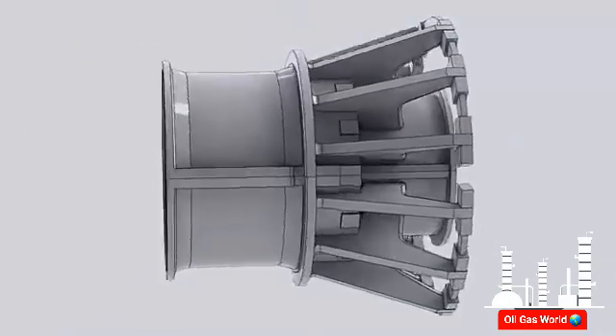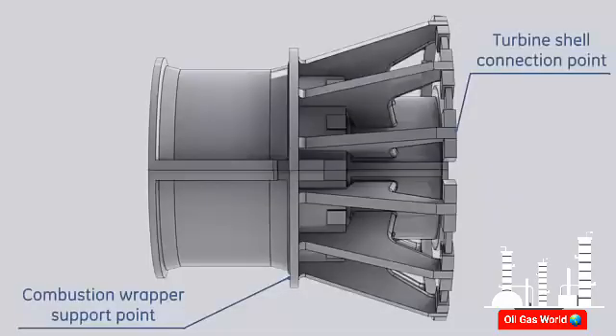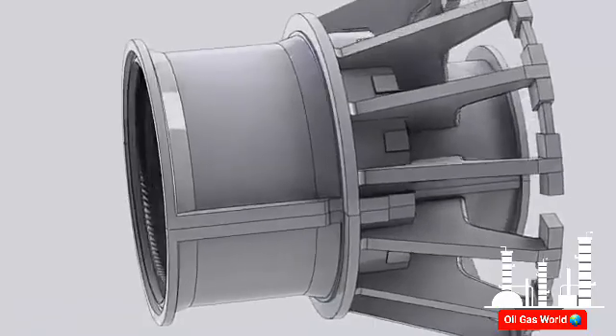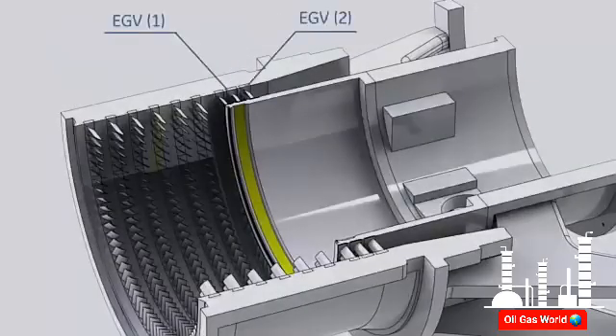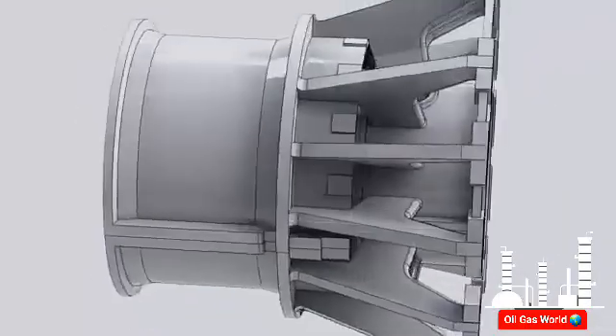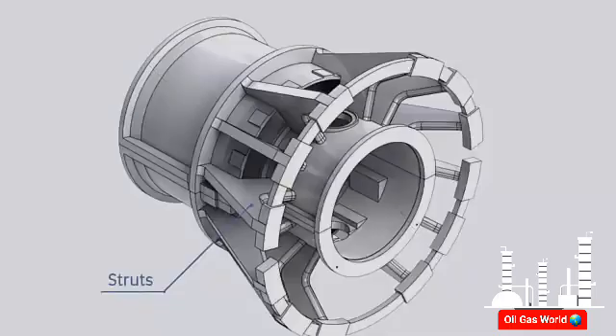The discharge casing is the final portion of the compressor casings and the largest single casting. It is the keystone of the gas turbine structure, connecting the compressor to the turbine section and supporting the combustion system. The discharge casing contains the last seven stages of compressor vanes and two rows of exit guide vanes. It consists of outer and inner cylinders connected by 12 struts, which flare out to meet the large diameter of the turbine shell while providing spacing for transition pieces in between.